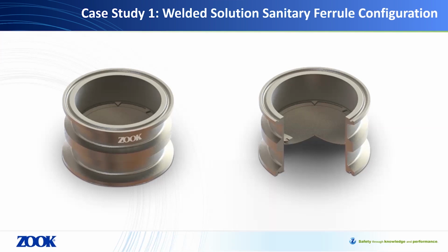This solution was designed to fit into the installation with no changes required to piping and was able to be integrated in minutes. While traditional rupture discs are available in the market, the downstream leak tightness is something unique among some designs of the welded solutions product family.